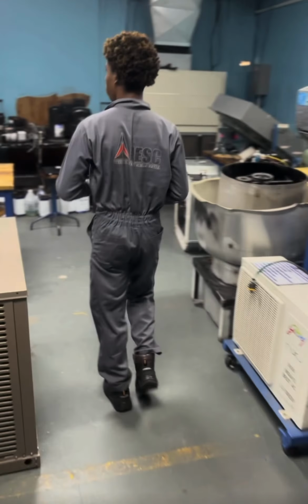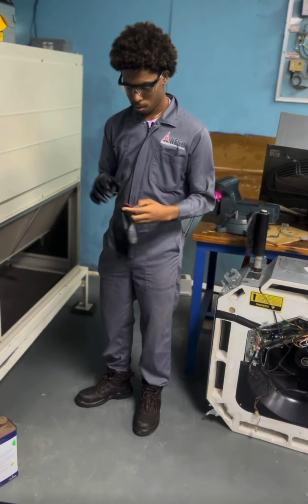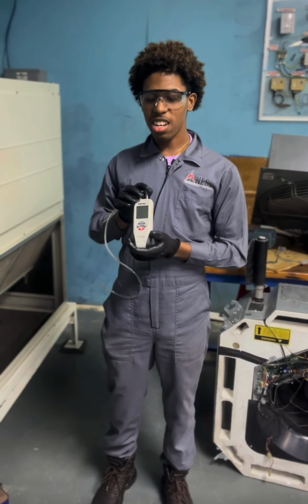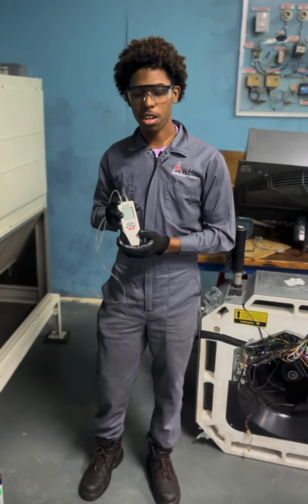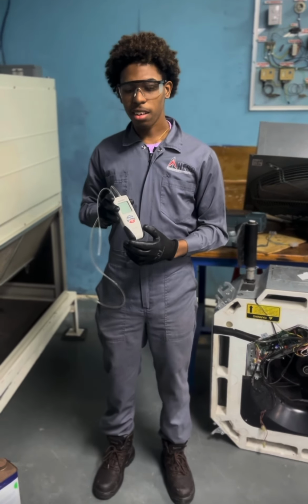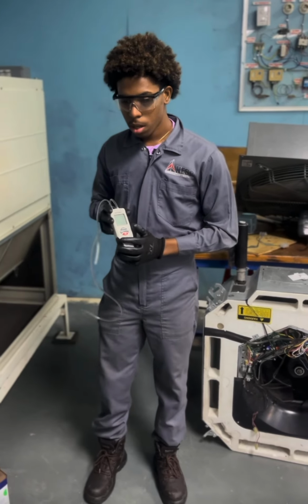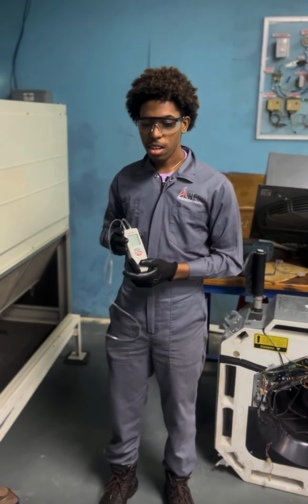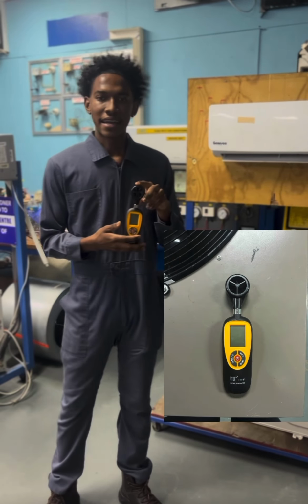Proper system balancing improves overall performance by ensuring the system operates as designed. Balanced systems are more efficient, reliable, and comfortable. The manometer is a diagnostic instrument used in HVAC systems to measure air or gas pressure. It is commonly used to check static pressure and verify proper airflow, which is essential for efficient heating and cooling performance. An anemometer is used to accurately measure wind speeds.